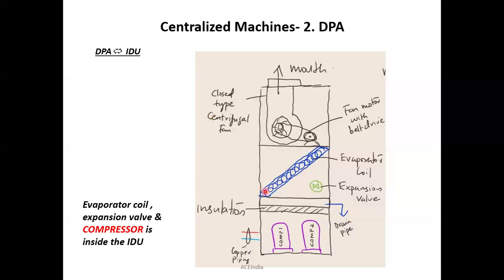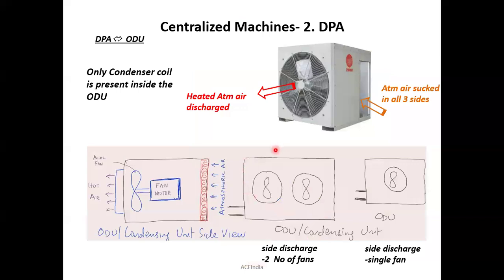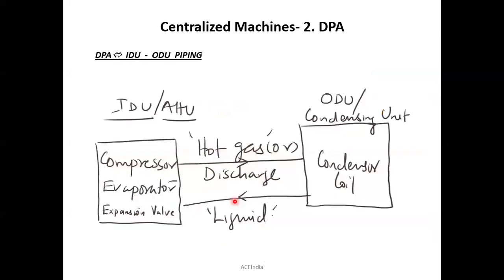Okay, that's it guys. So this is the idea of a DPA indoor unit typically. Here the only element which comes inside the indoor unit is a compressor. Okay, the other connections are still the same. And next, it's about the ODU. As I mentioned before, inside the DPA ODU you can't see any kind of compressor. The only elements are an axial fan with a fan motor and the condenser coils. All right. So this is how it should look, a side discharge assembly with a single fan or double fan.